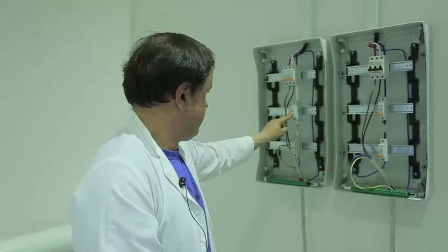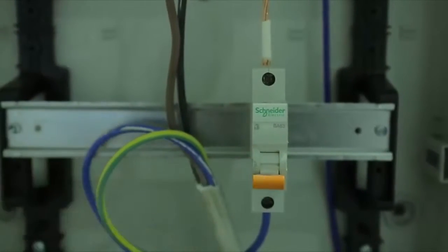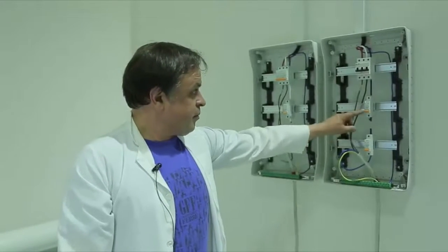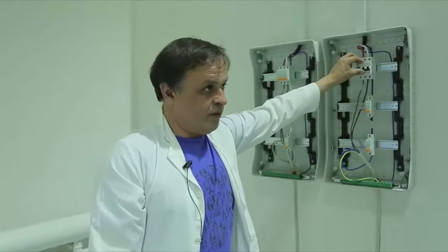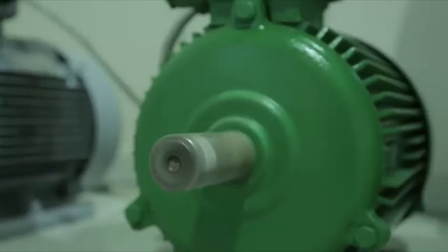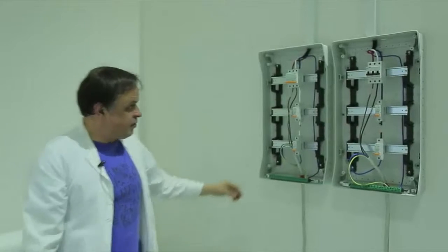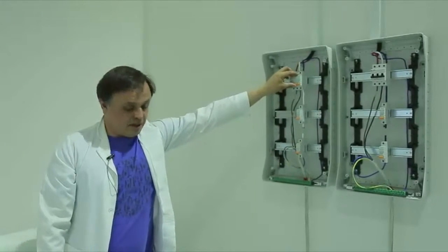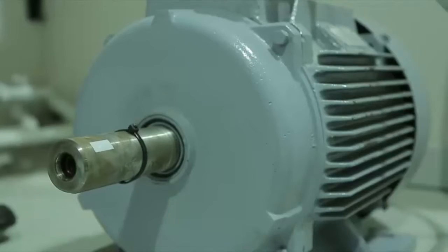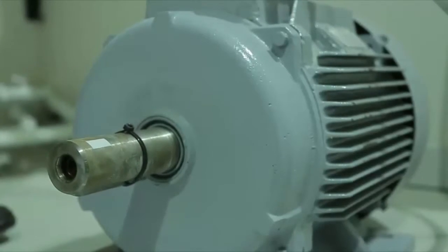Now, disconnect a phase in the supply circuit of each motor. Turn on the asynchronous motor of new design without phase. The motor is working. Turn on the standard asynchronous motor. In such an operation mode, the motor either fails or will be forced to turn off.